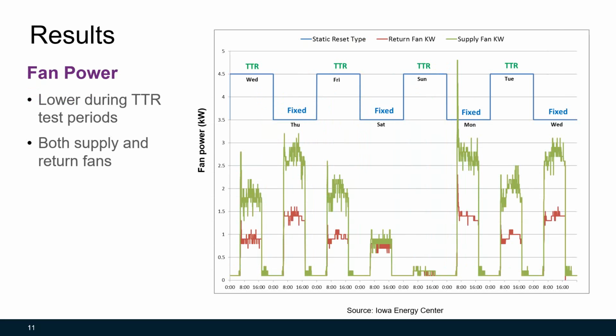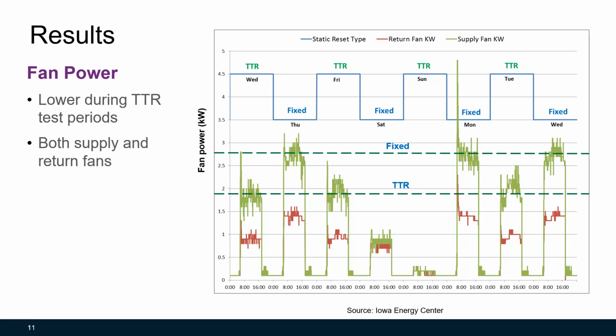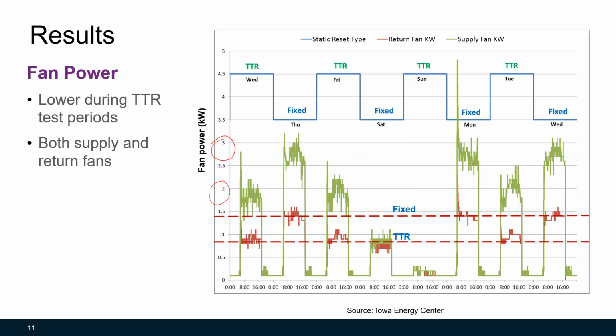Now let's look at the fan power comparison for the two different control methods. We alternated the tier trim response method and the fixed static pressure method every day. The green curve represents supply fan power, and the red curve represents return fan power. We can see that for the tiered trim and response method, the average fan power for the supply fan is about 1.8 kilowatts. And for the fixed static pressure control, it's about 2.8 kilowatts. Similarly, the average return fan power for the tiered trim and response method was also much lower.